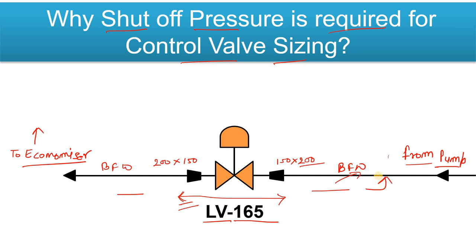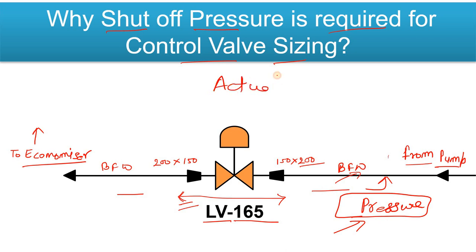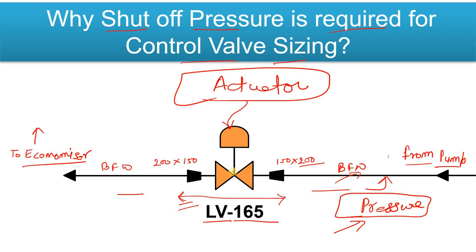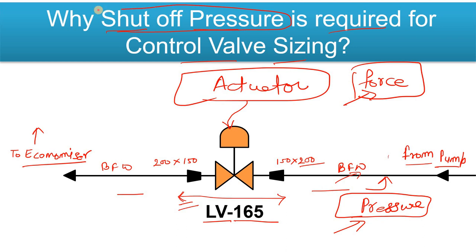The shutoff pressure is the maximum pressure that could exist within this line. The significance of the shutoff pressure is that it is used to design and size the control valve actuator. The actuator helps the control valve to open or close. When the actuator operates, it lifts or lowers the valve's stem and disc. To lift the stem and disc, a certain force is required — and to calculate this force, the shutoff pressure is needed.